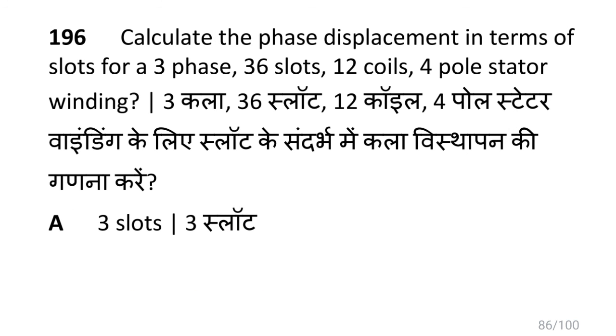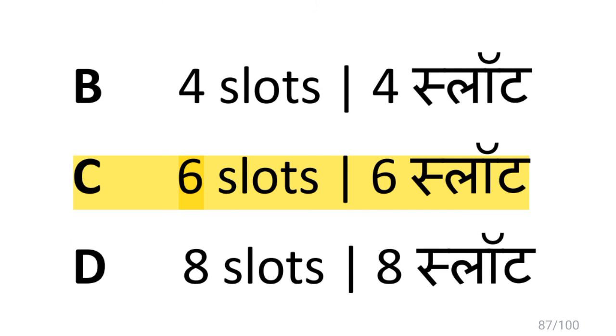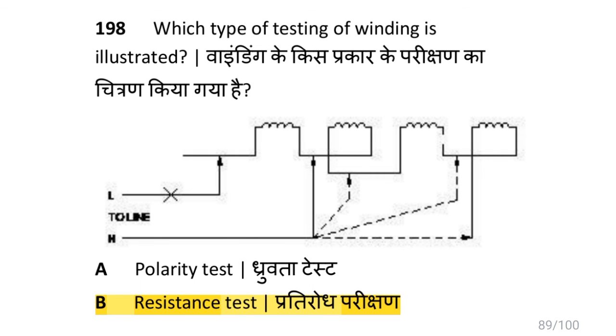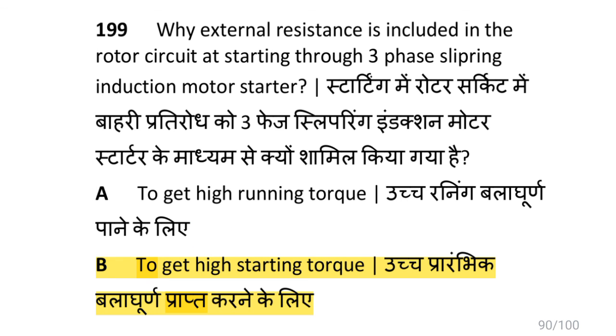Calculate the phase displacement in terms of slots for a three phase, 36-slot, 12-coil, 4-pole stator winding: the answer is 6 slots. The AC motor winding type where the number of coils per pole per phase is more than one arranged in different slots is distributed winding. The type of testing illustrated is resistance testing. External resistance is included in the rotor circuit at starting through a slip ring induction motor starter to get high starting torque.